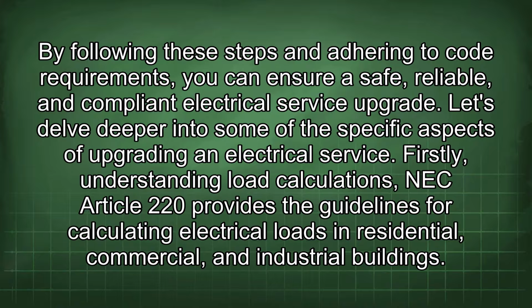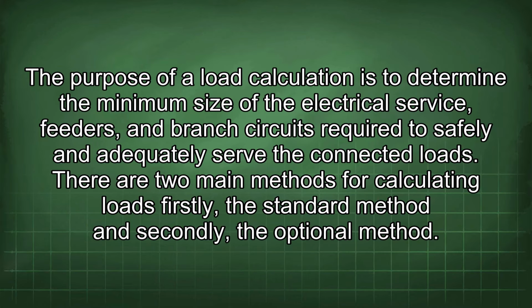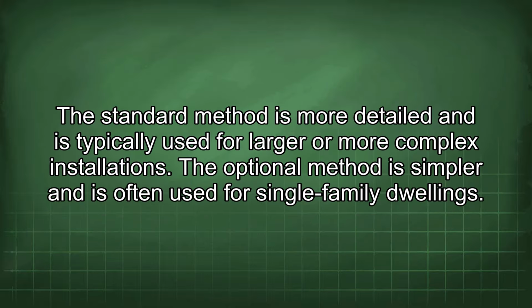Let's delve deeper into some of the specific aspects of upgrading an electrical service. Firstly, understanding load calculations. NEC Article 220 provides the guidelines for calculating electrical loads in residential, commercial, and industrial buildings. The purpose of a load calculation is to determine the minimum size of the electrical service, feeders, and branch circuits required to safely and adequately serve the connected loads. There are two main methods for calculating loads: firstly, the standard method, and secondly, the optional method. The standard method is more detailed and is typically used for larger or more complex installations. The optional method is simpler and is often used for single-family dwellings.